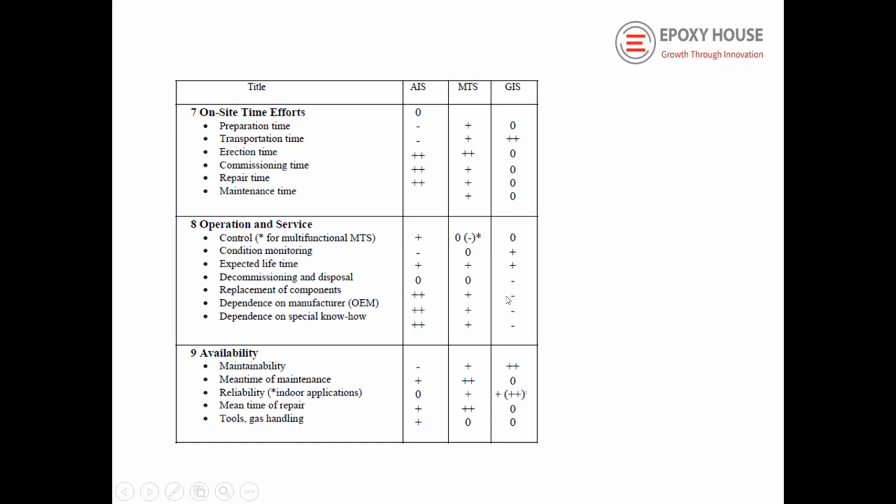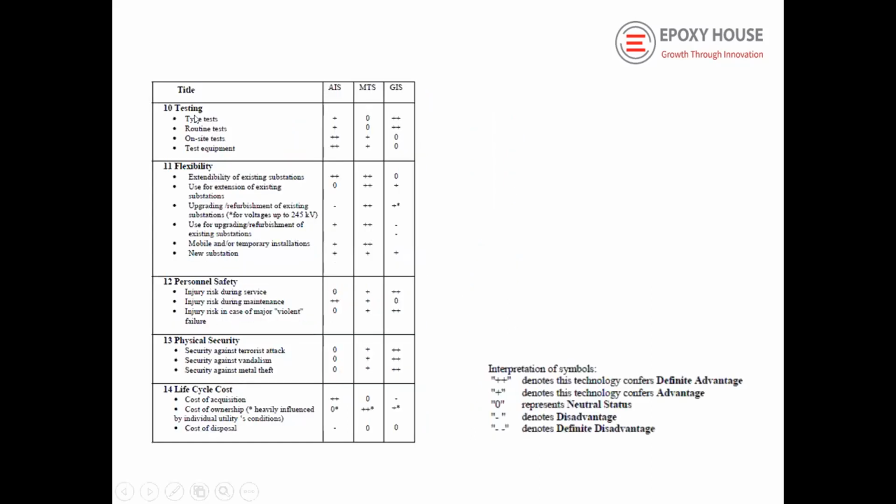It can be, because nowadays, based on the new technologies, condition monitoring and all is very easy in the gas insulated switchgear. Here in the LCC, we put all the components required for condition monitoring. We can do that. So now the testing, flexibility, personnel safety, physical security, and all those points, GIS is superior compared to AIS.